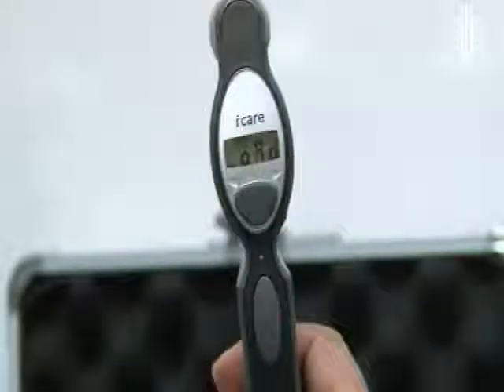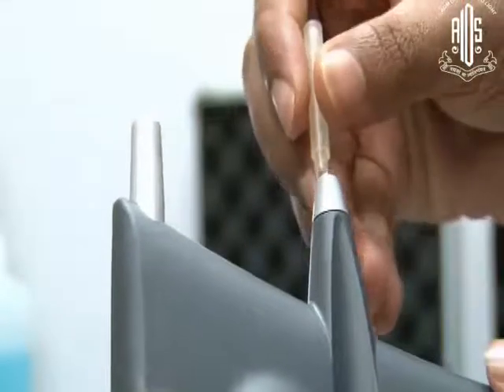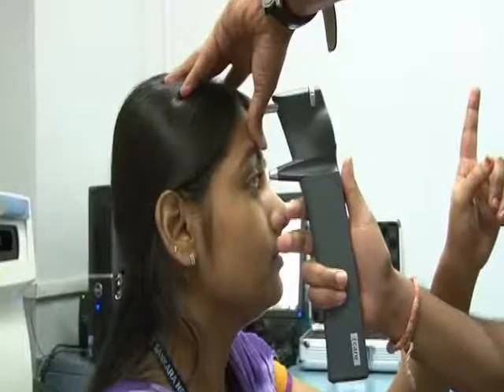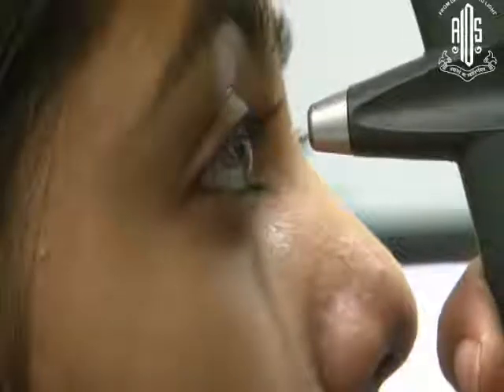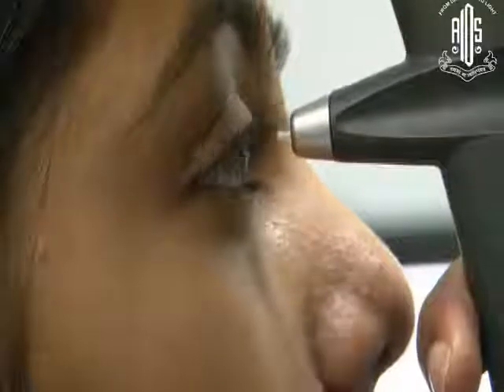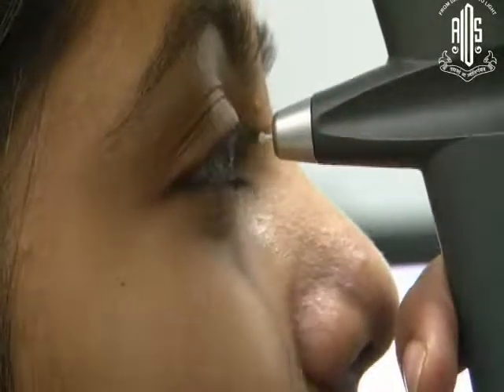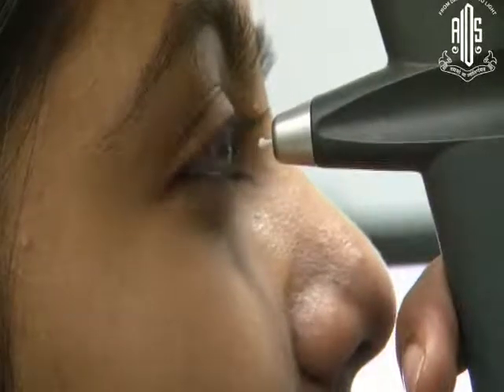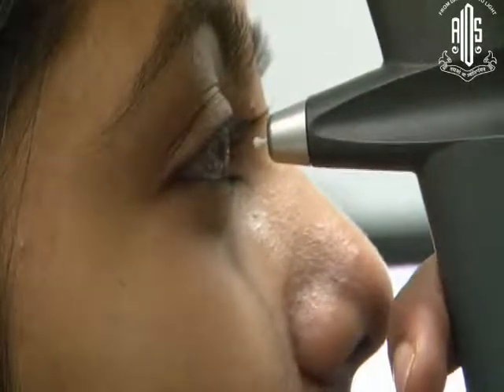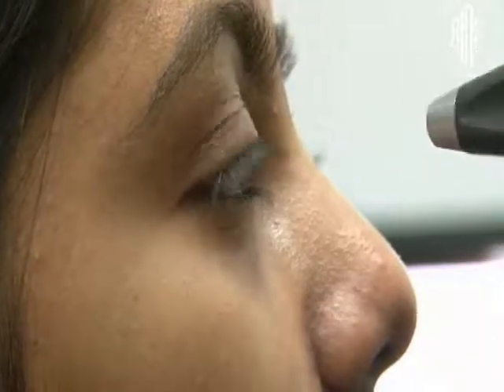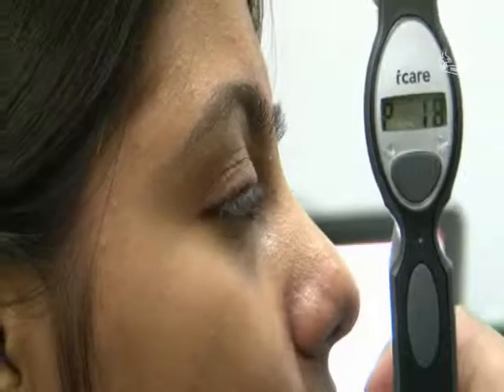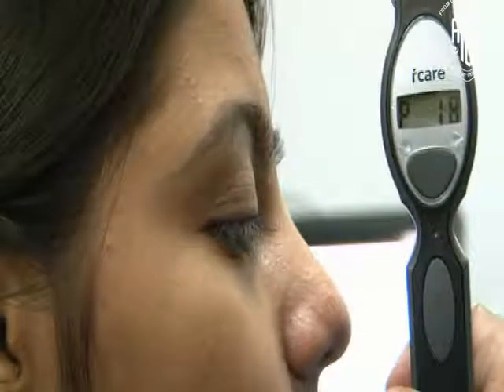So this is the probe tip that comes inside that. The probe tip is not sterile, and that should be remembered. You load it onto this device like that. You rest it against the forehead, and you can see the bouncing off the cornea. Again, because this is a very, very brief applanation moment, you need to take multiple readings, and what is recommended is 6 readings. Once you finish 6 readings, you will get a P over there and a value of whatever the reading is. You will also see a black line which may be at the bottom, at the middle, or at the top, which tells you how accurate that reading is.